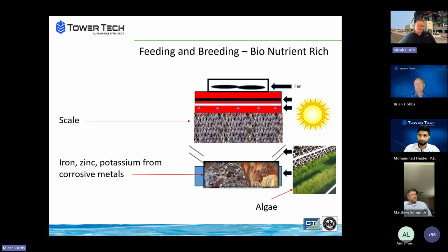When I walk around, even in Oklahoma City, where I live, or any city, you go look at a cooling tower and the picture on the top, you're probably going to see something similar occurring on the cooling tower. I'm going to say 90% plus of the cooling towers I come across, you're going to see something like this picture. Yes, varying degrees, some cleaner than others, some of them completely clogged with scale and corrosion. Yep, that's correct.